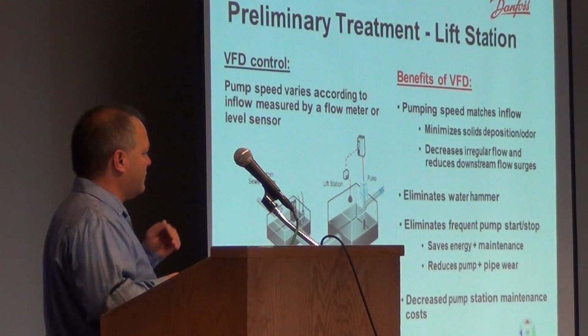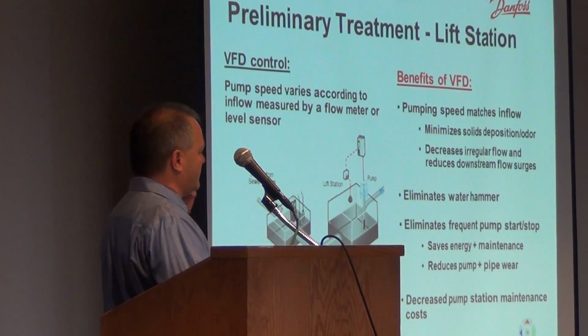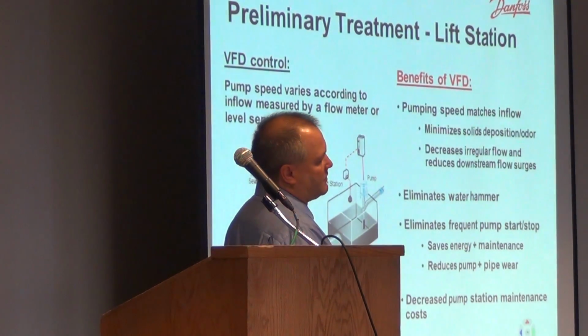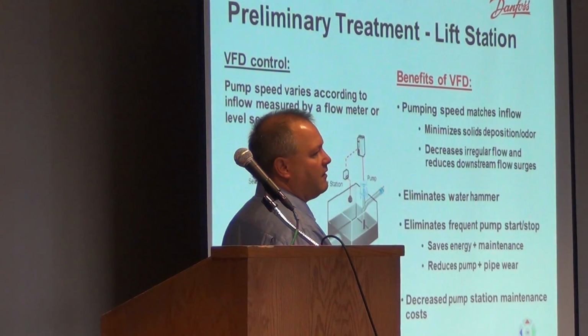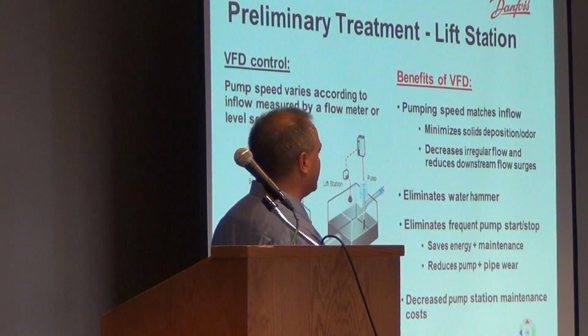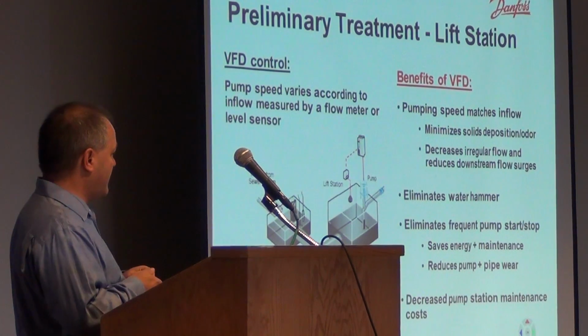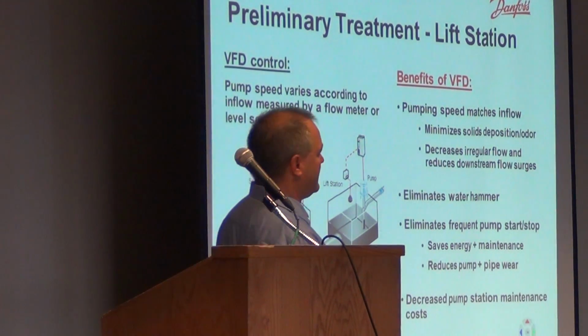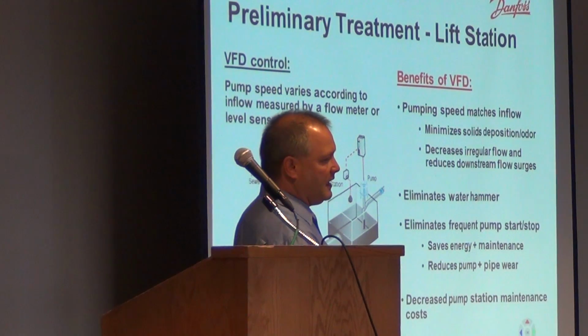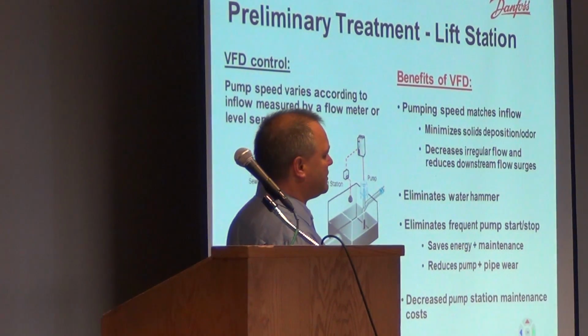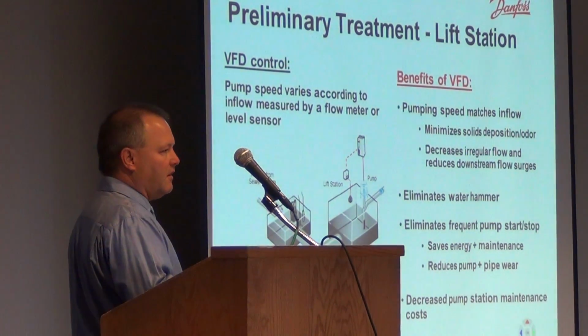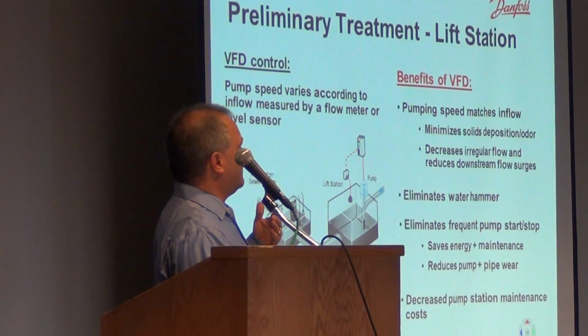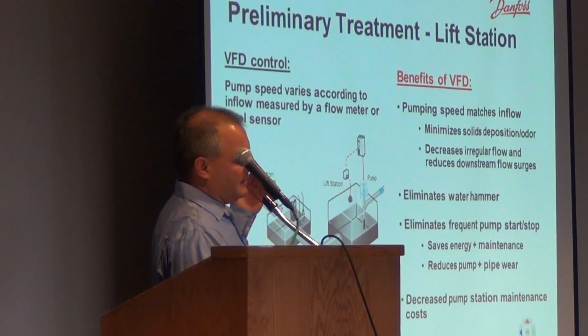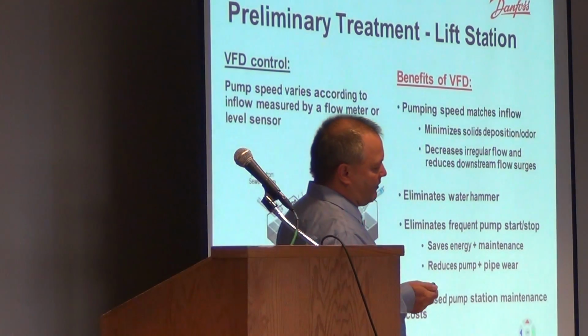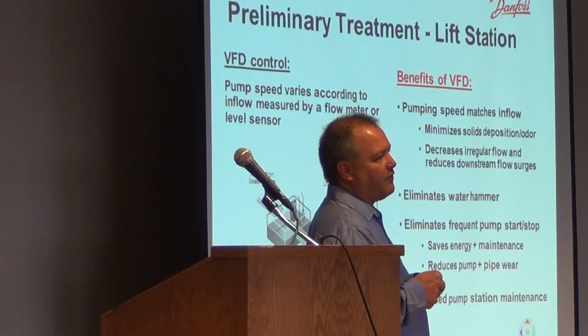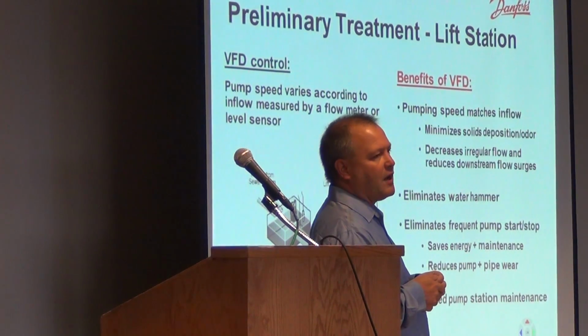The drive drastically reduces the cost of the energy to run that motor. It also gives you a constant flow to the system so that you're not having these large slugs of waste and water coming into your system. As I stated earlier, it eliminates water hammer, so pipe breakage, check valve sticking, frequent pump starts and stops. The drive will actually cause the motor to run longer, but it also maintains a constant speed and you will wear less on your motor. It's like driving your car with your foot all the way down on the floor and using the brake to set your speed.